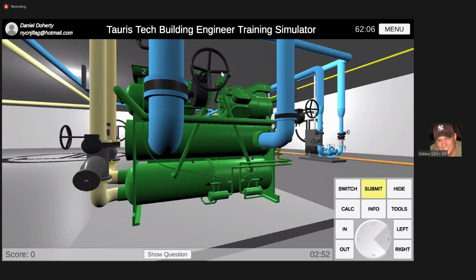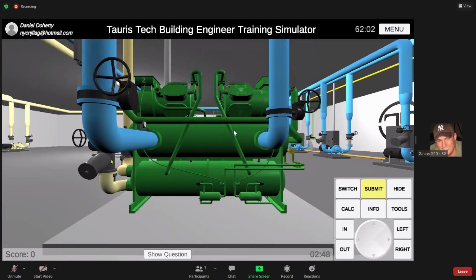All right, so high pressure, high temperature, superheated vapor comes out of your compressor into your condenser. The vapor condenses, turns into a liquid refrigerant. That liquid refrigerant is then subcooled right here. You got a line right here coming down from underneath. That's your subcooled liquid line. That subcooled liquid line comes up through your king valve, through your strainer, out. There's a solenoid right there. We'll get back to that. We'll get back to the king valve.